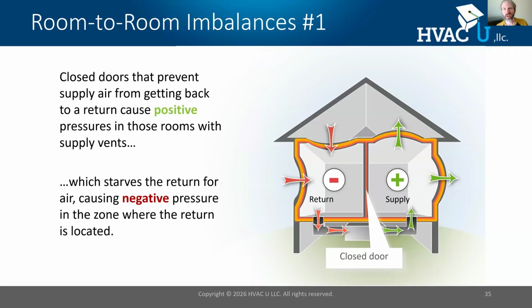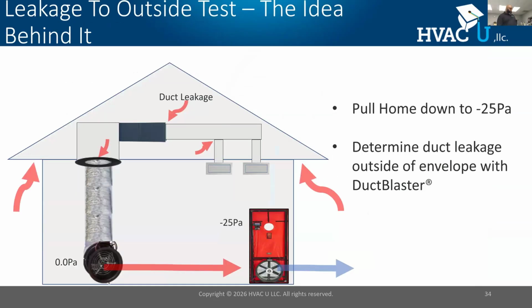Can I chime in real quick, Bryn? Yep. Back to the other point, a lot of people forget that under LEED Energy and Atmosphere minimum energy performance, total duct leakage to outdoors is mandatory. You have to do these two tests at the same time. Sometimes we'll see the duct blaster test done and the blower door test done, and then someone asks, did you do them at the same time? No, you have to go back, right?